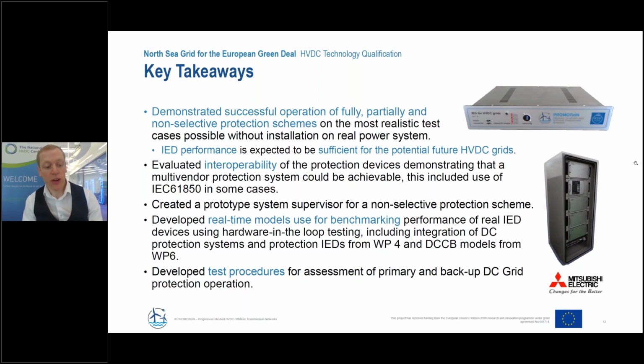We created a prototype system supervisor for the non-selective protection scheme, and developed real-time models for future benchmarking of other real IED devices using hardware-in-the-loop testing. This included integration of the DC protection systems and protection IEDs from Work Package 4 and the breaker models from Work Package 6, as well as our test procedures for assessment of primary and backup protection operation.